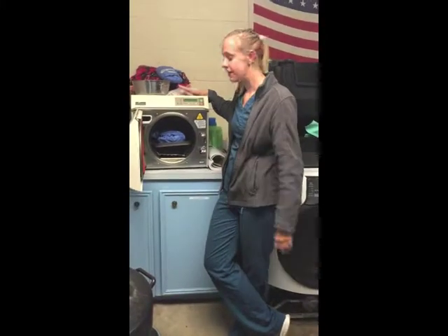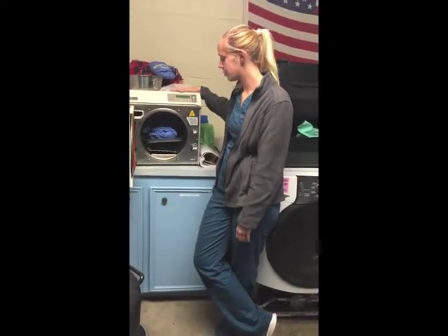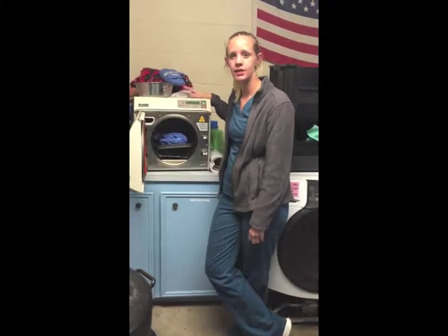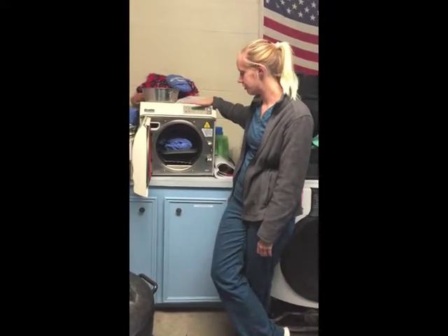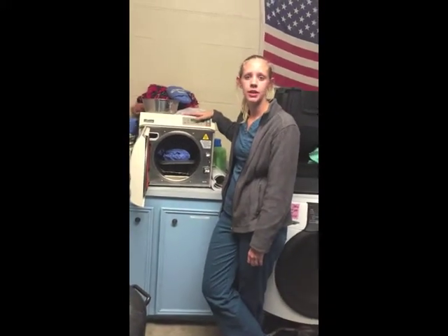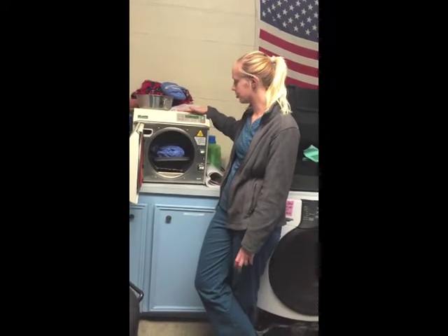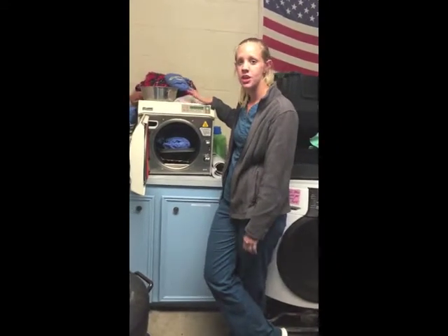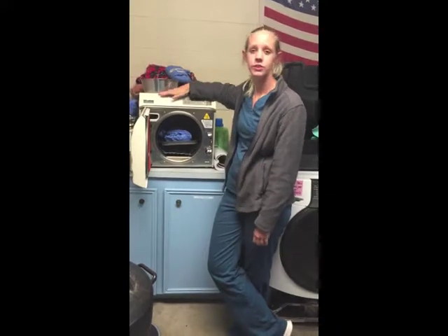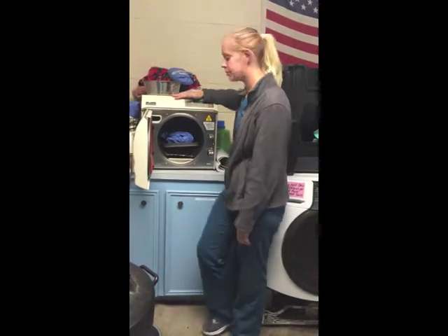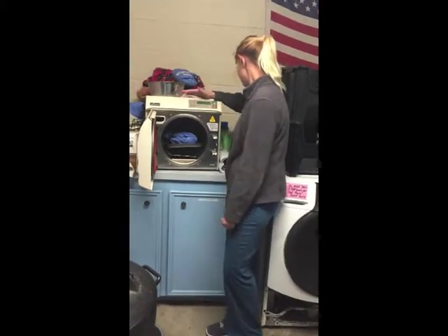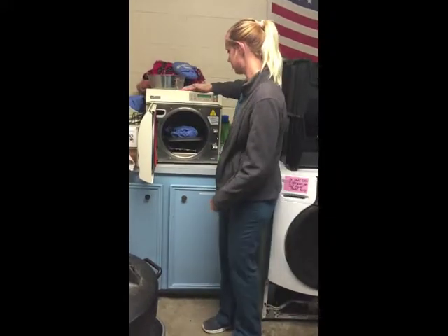So about the average time for an autoclave to complete its cycle is about 15 minutes. And depending on what you have and how thick the item is, it may be sterilized between the 3 to 15 minute range. The typical temperature is 250 to 270, and the typical pressure is 15 to 27 pounds.